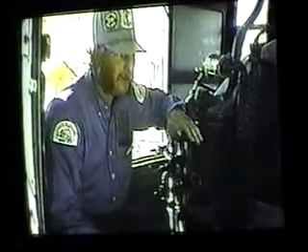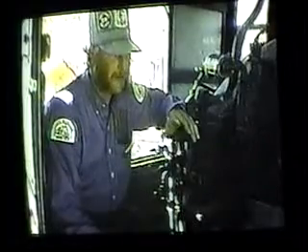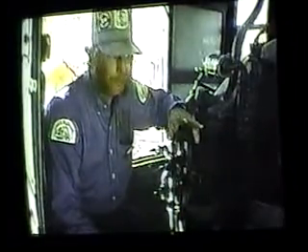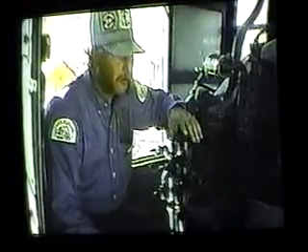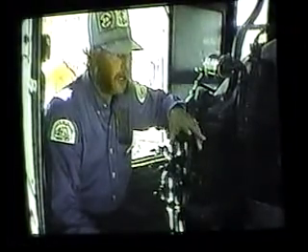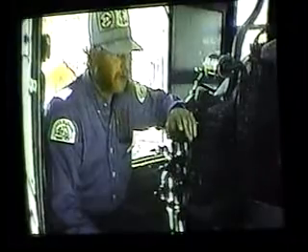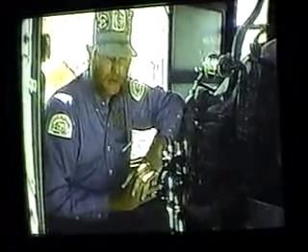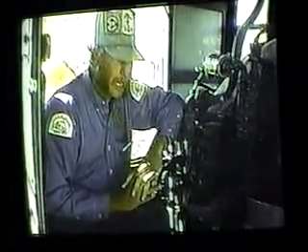Now, something also to remember when you've got the fuel oil tank here: fuel oil expands. Heating the oil increases the volume and decreases the specific gravity and weight per gallon through the expansion of the oil. Decreasing the temperature decreases the volume of the oil and increases the gravity and weight per gallon. Oil changes about 1% in volume for every 25-degree rise in temperature.